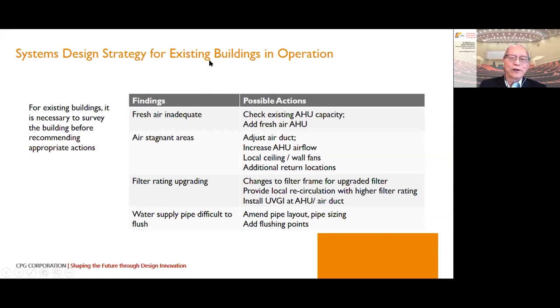For existing buildings, in order to be pandemic resilient, do we need to change the building services systems? We have to do a survey. Maybe we can just adjust the AHU fan or add fresh air handling units to complement the existing ones, adjust the aircon outlets, add return air locations, add UVGI at the air handling units or inside the air ducts, and for water supply pipes, maybe strategically locate flushing points to provide efficient flushing and save on time and labor. These are the possibilities.